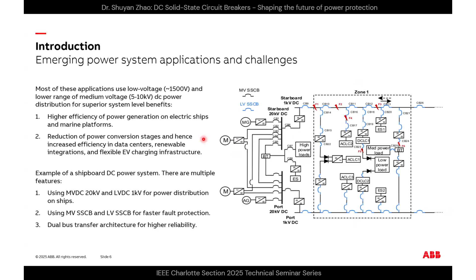And here, the right side shows an example of a shipboard DC power system, and there are multiple features here. It uses medium voltage DC, 20 kilovolts, and LVDC, 1 kilovolt, for power distribution on ships, with medium voltage solid state circuit breakers here, and low voltage solid state circuit breakers here for faster fault protection. Another feature of the system architecture is, as you can see, the dual bus transfer architecture, 1 and 2, for higher reliability.